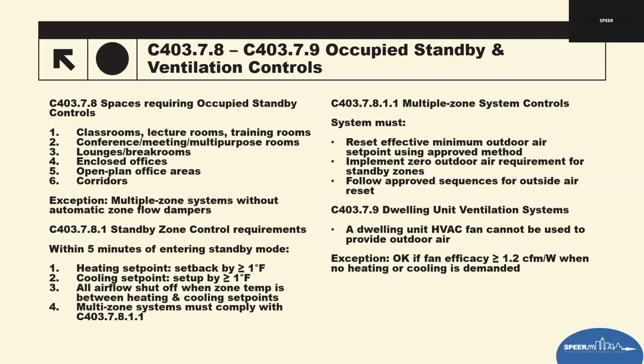And then multi-zone system requirements. If it's a multi-zone system, standby mode must also include a reduction in outdoor air. So now we're tying more systems into this. So the system must reset the effective minimum outdoor air set point to account for zones that are unoccupied. Key requirement: standby zones must have 0 outdoor air supplied to them when they're in standby mode.